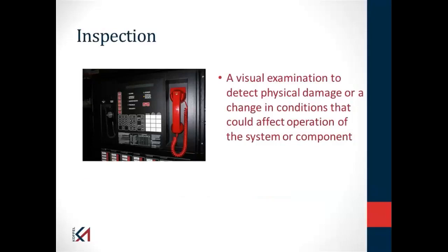So let's first talk about what is inspection, testing, and maintenance. Inspection is the visual observation that what you have appears to be in proper operating condition. And when it comes to NFPA 25, that's very critical because there is language in the administrative chapter of NFPA 25 that says the inspector is not required to verify the adequacy of the design of the system. In other words, don't expect a contractor that you hire to do inspection services under NFPA 25 to tell you if that sprinkler system's adequate for the hazard being protected, that you have sprinklers everywhere you are supposed to have them.